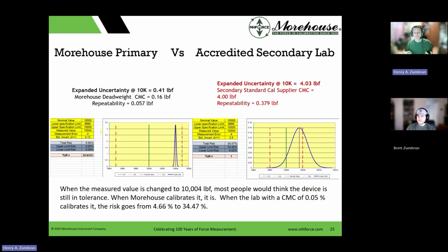We at Morehouse, with dead weight machines, because we have these high TURs on this device, can still say that instrument's in tolerance. Another supplier that's using that CMC, it's a good machine, I don't want to knock it, it serves its purpose. But if you're trying to say something's good to 0.05% and the best you can do is 0.04%, you do not have much room on either side to say that device is good if you're applying any type of guard band whatsoever.